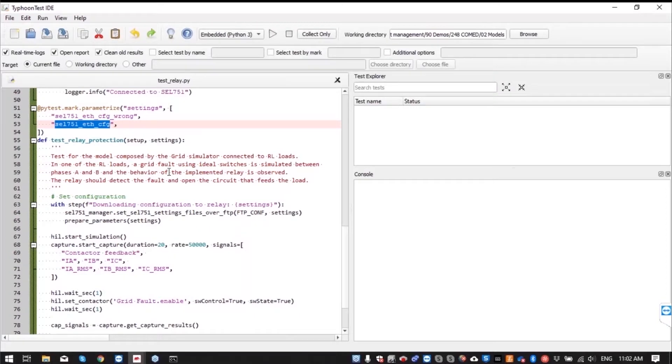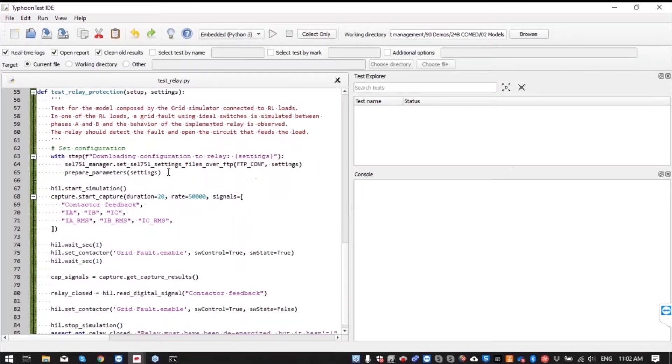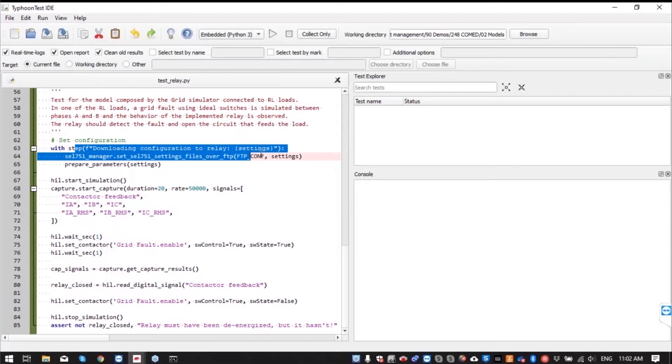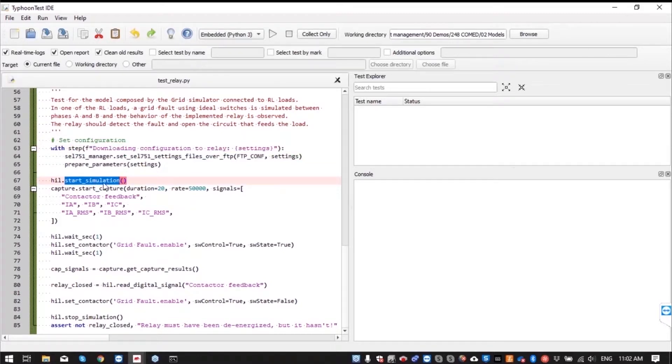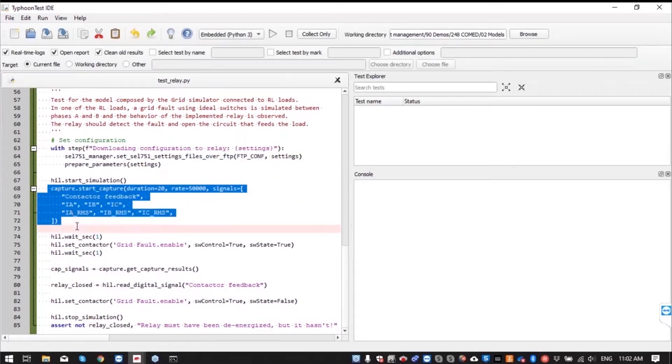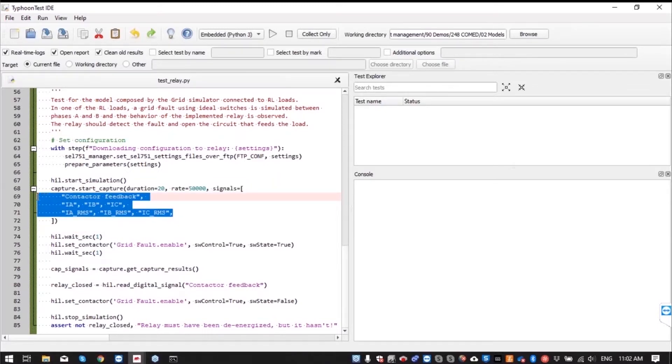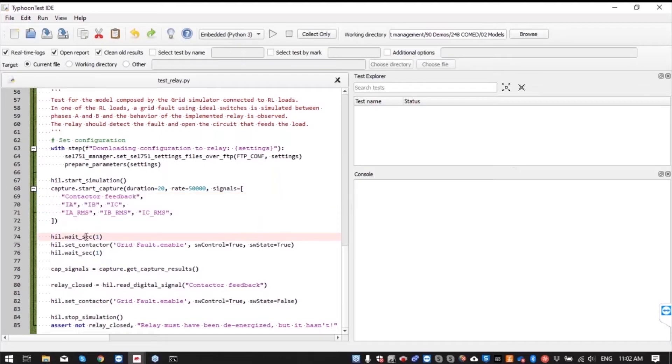The logic of the test starts with downloading the configuration to relay, starting the simulation, starting the capture of the signals we are interested in. We wait one second before setting the grid fault to short circuit to that line where we have the second load.